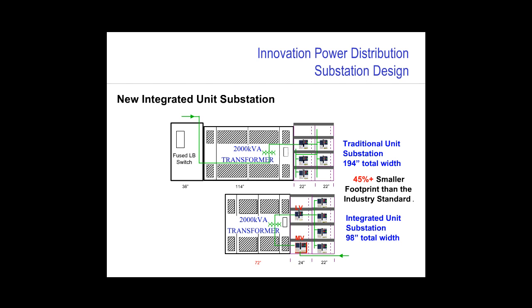designs. In the lower diagram, you'll notice I'm using the vacuum medium voltage breaker on the primary, but I also show a secondary low voltage main circuit breaker. I would probably opt to remove this breaker from the assembly and instead install current transformers, tripping the primary breaker as we've discussed before.